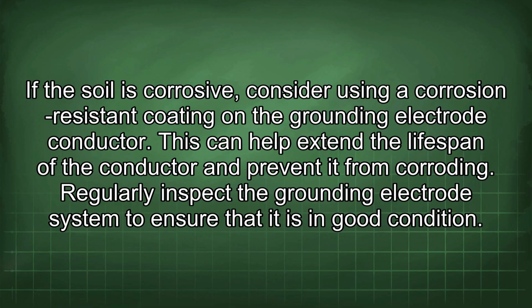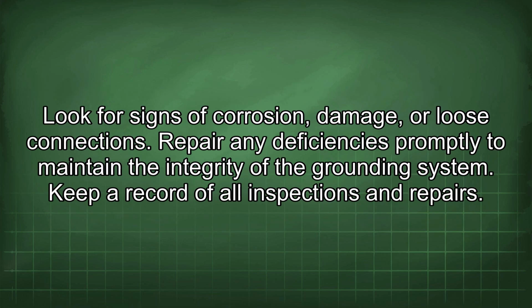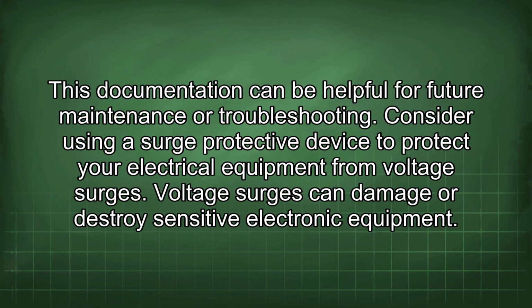Regularly inspect the grounding electrode system to ensure that it is in good condition. Look for signs of corrosion, damage, or loose connections. Repair any deficiencies promptly to maintain the integrity of the grounding system. Keep a record of all inspections and repairs. This documentation can be helpful for future maintenance or troubleshooting.